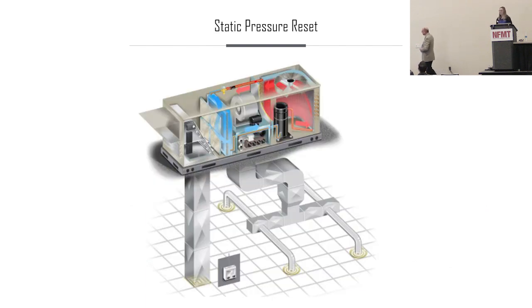For this unit, it's a DX cooling unit, and we came in and, trying to be snazzy, added programming to reduce some energy on the fan running. Everything goes back to fan laws. So we try to do a static pressure reset instead of running that fan at a constant static pressure. However, it was going to void the warranty if we did that while the compressors were running, because the compressors required a certain amount of airflow going across them. So we found a loophole and talked to the manufacturer and asked, if it's in air side economizer mode, can we reset the fan to slow down? The compressors are locked out. That's not going to be an issue anymore. After talking to them, they were like, well, I guess so. It doesn't say anywhere that you can't do that.